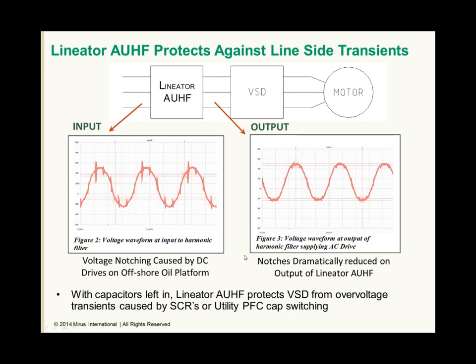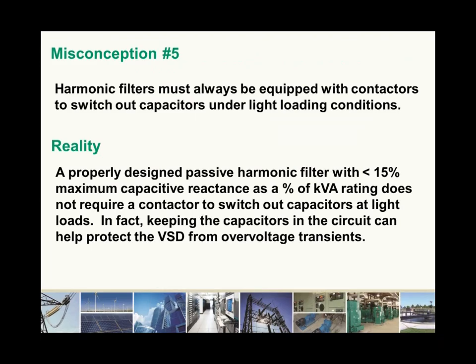We've run into situations where people have insisted on putting contactors on the Lineator filter. They lose this advantage because if they're switching out the capacitors under light loads, if that's when the power factor correction capacitor switching occurs, then these overvoltage transients will pass right through and affect the downstream equipment. So misconception number 5 is that harmonic filters must always be equipped with contactors to switch out capacitors under light loading conditions, when in reality a properly designed passive harmonic filter with less than 15% maximum capacitive reactance as a percent of the kVA rating does not require a contactor to switch out capacitors at light loads. In fact, keeping the capacitors in the circuit can help protect the VSD from overvoltage transients.